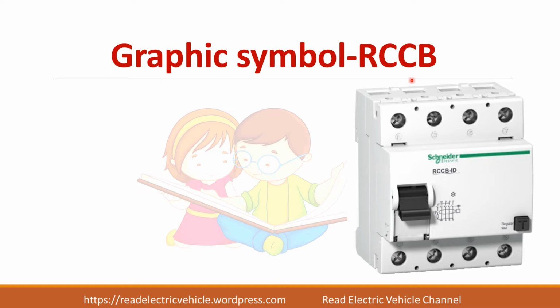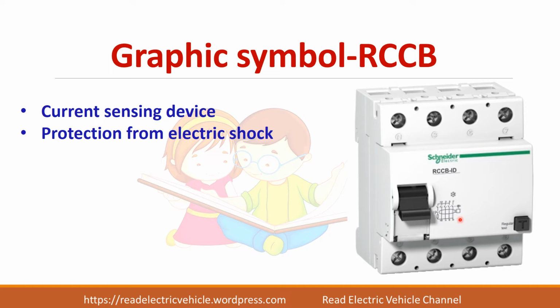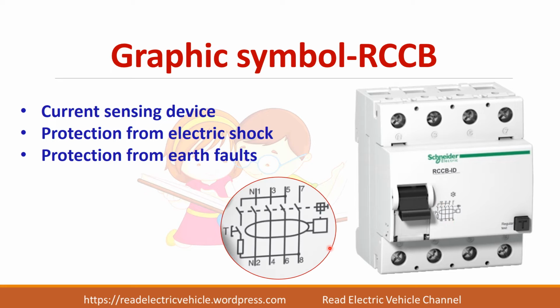If you see the graphical symbol of residual current circuit breaker, so RCCB, we know it is a current sensing device because it will sense the current, leakage current. So this is used for protection from electrical shock and earth faults. So here you see the picture, it is like a loop. It means that it is sensing the current. So for each device there is a different set of graphical symbol used.